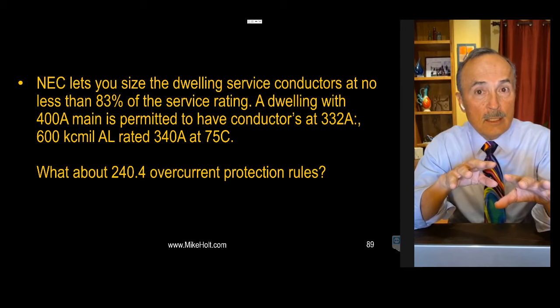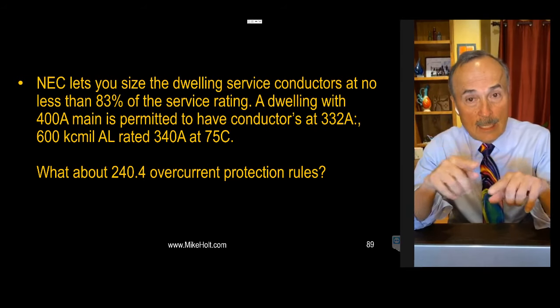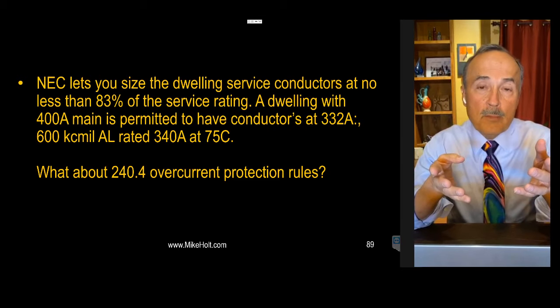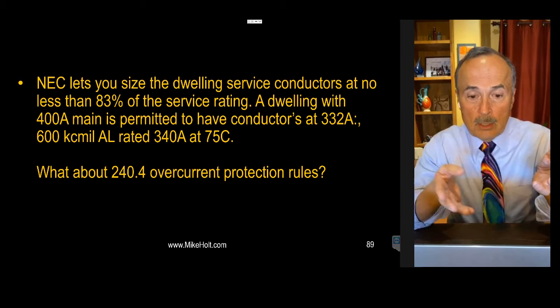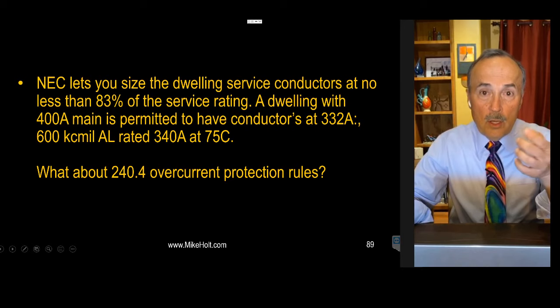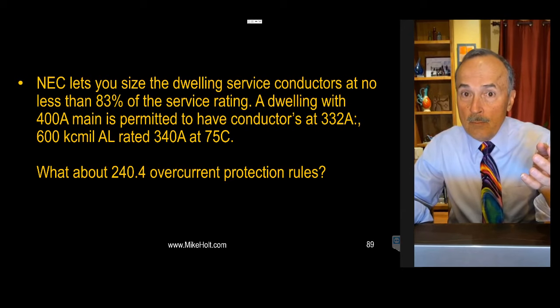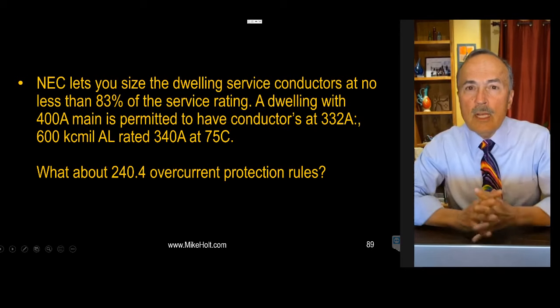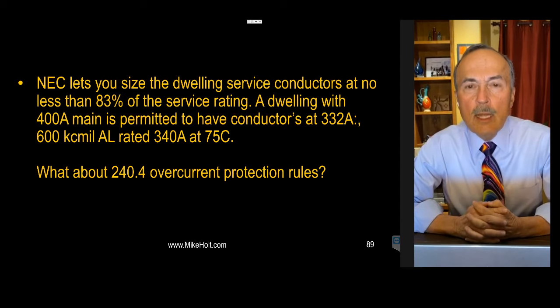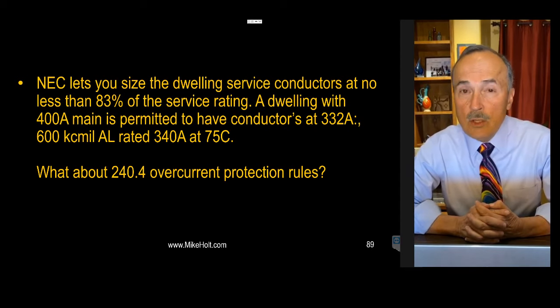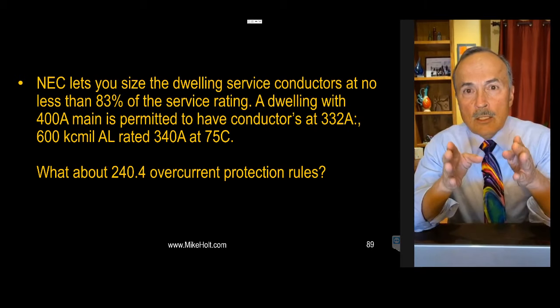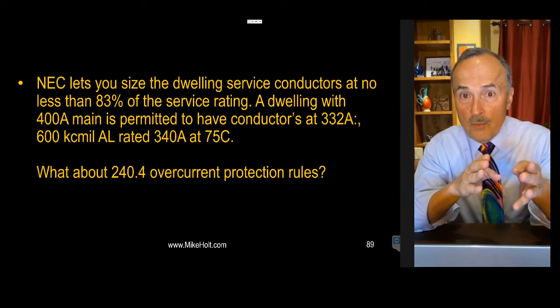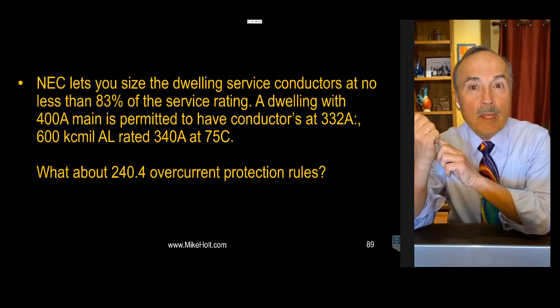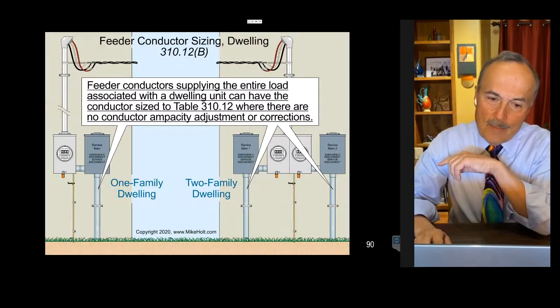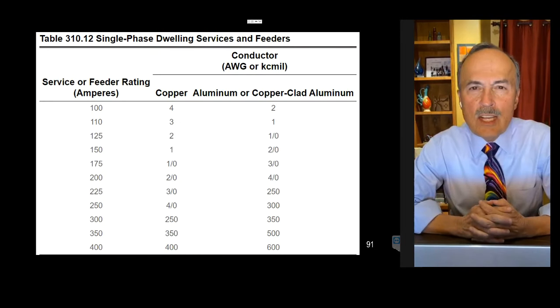Section 240.4 tells us conductors must be protected at their ampacity. Then there's a rule, 240.4(B), that says if the ampacity of the conductor doesn't correspond to a standard size, which is identified in 240.6, you can use the next size up. Okay, great. But take a look at the slide here. In 240.6, there's a 300 amp protection device, a 350 and a 400 ampere. This is a violation of the code. And it blew me away that for 100 years, maybe more, this has always been wrong.